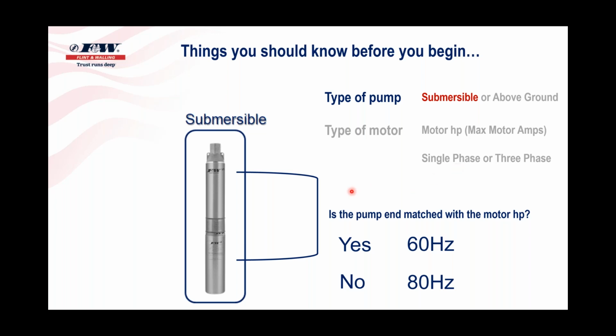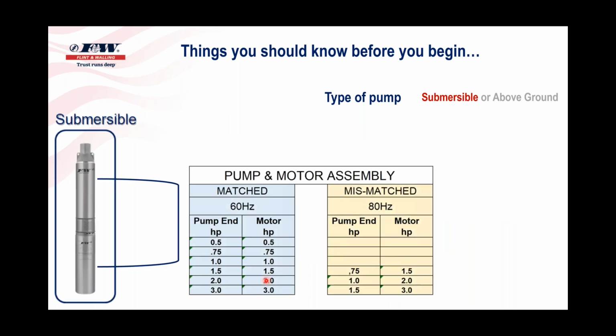So basically, when it comes up and asks you what frequency you want your drive to run at, it's going to be 60 hertz if the pump end is matched with the motor. It's going to be 60 hertz, and if it's an above ground pump, it's going to be 60 hertz. And the only time we would run it at 80 hertz is if we mismatched the pump end to the motor. And the only time that Flint Walling ever did that was if you bought the package system. So hopefully I explained that clear enough that you understand what I'm talking about there. And I'll probably circle back on this as we actually look at the programming itself.